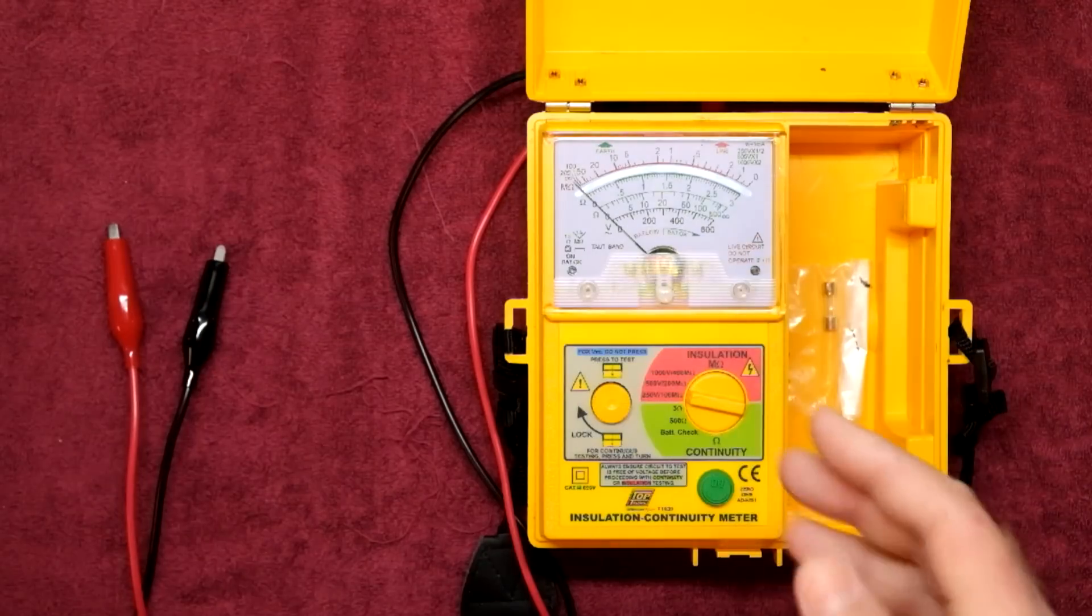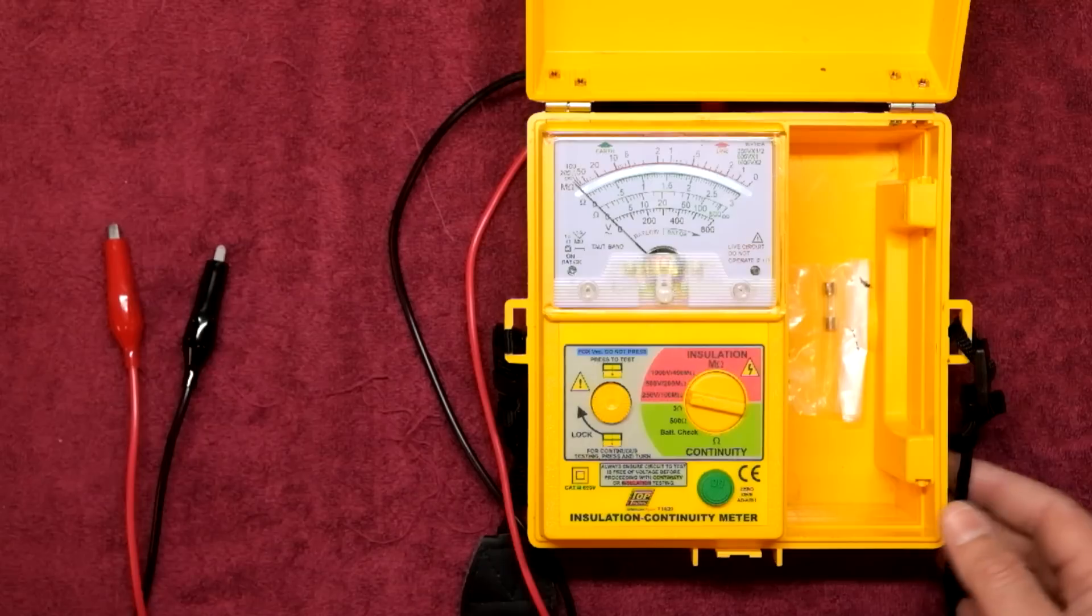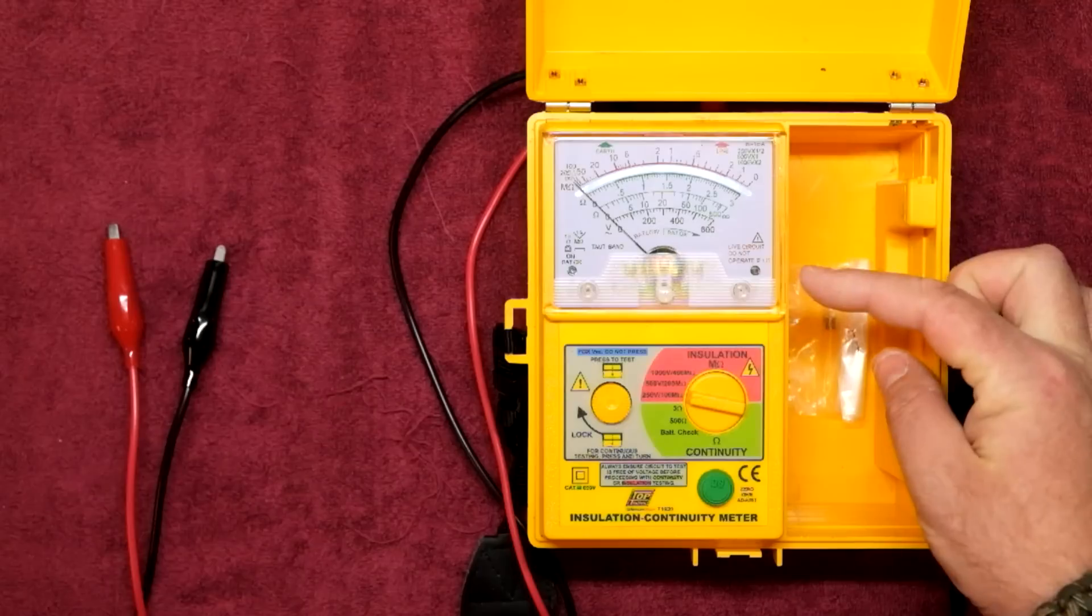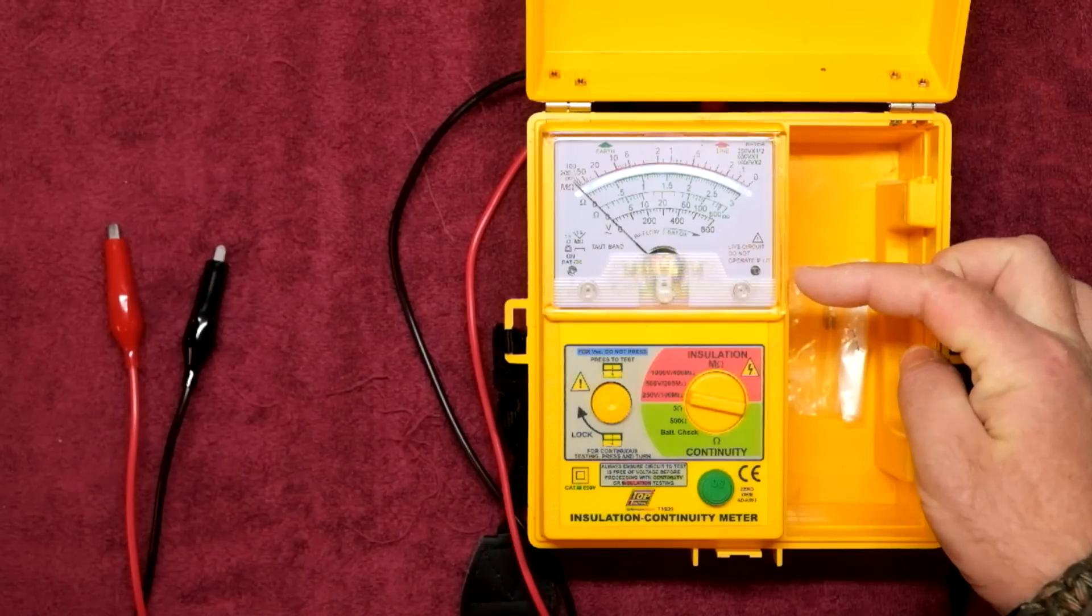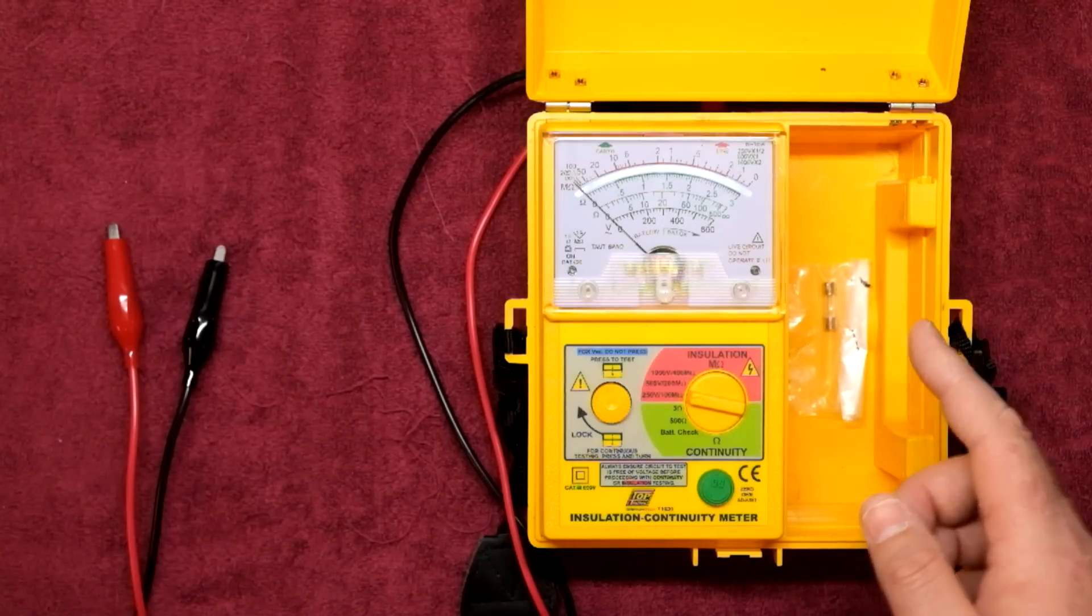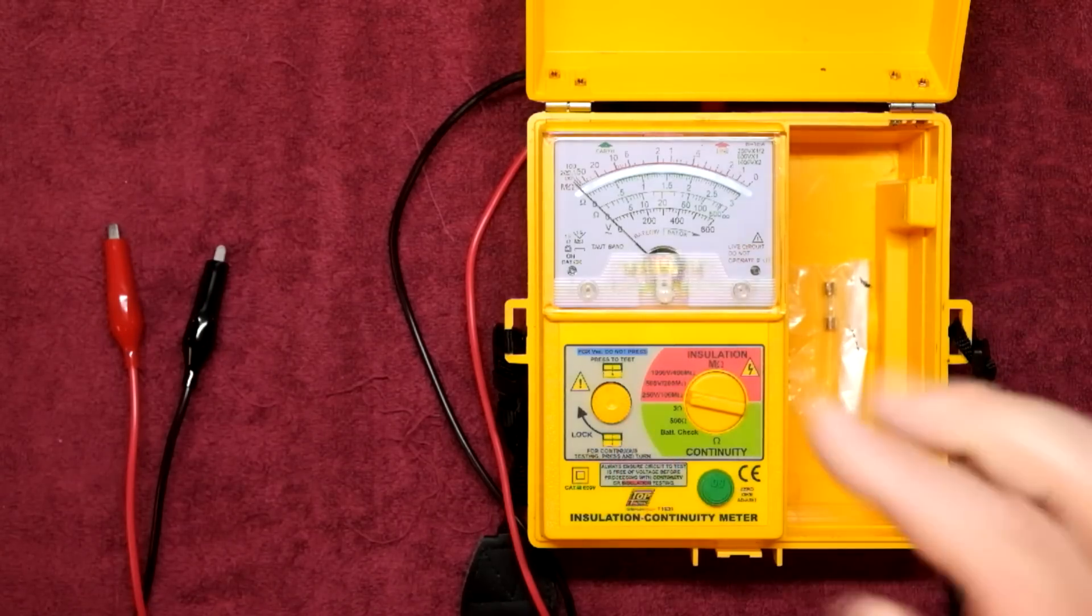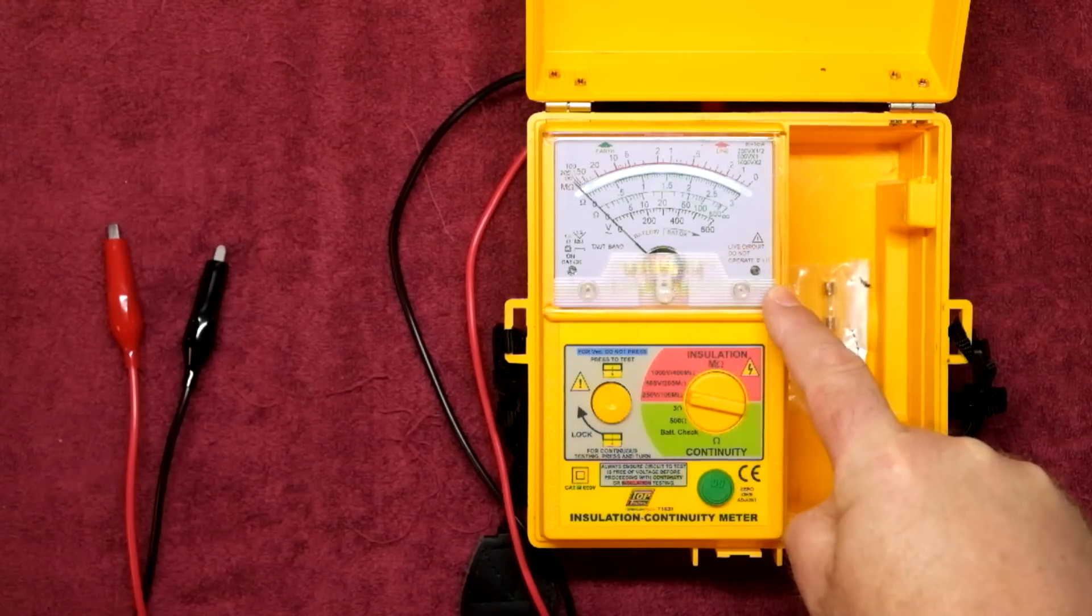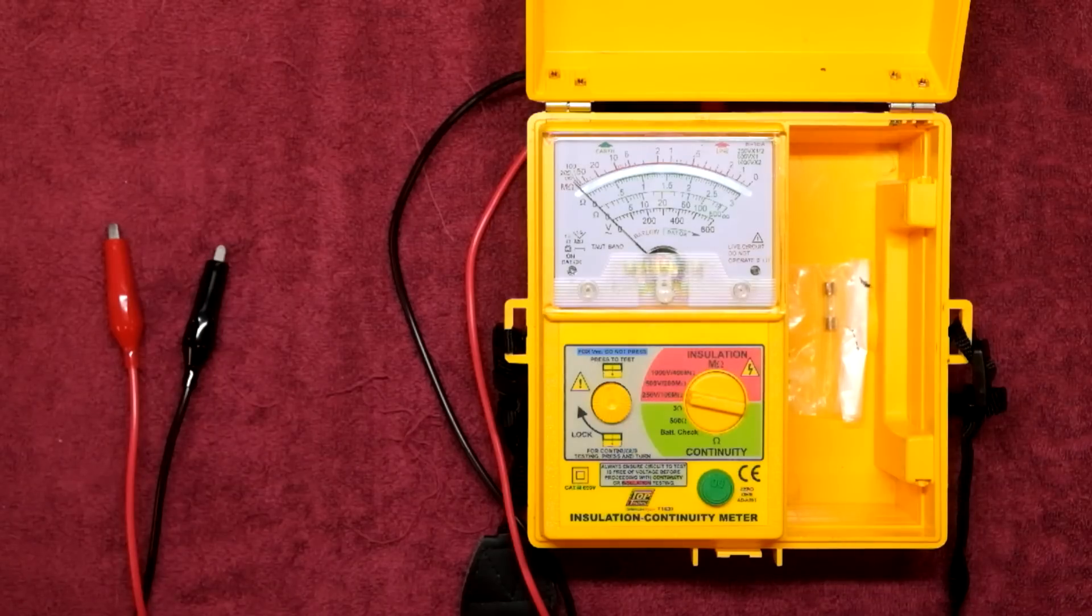And this has to be done on a dead circuit. So you must make sure that the power is off on the circuit before you go and do this. Otherwise you could be damaging some things. This meter does give you a warning: live circuit do not operate if lit. So if you happen to connect up it's going to give you a voltage reading and it's going to warn you not to push the test button. If you push the test button and it's live, you are going to damage the meter. Just keep that in mind. This is a common failure point with these sort of things. So yeah, there's not much else to be said for insulation resistance testing. I'm going to show you how useful it is for testing appliances next.